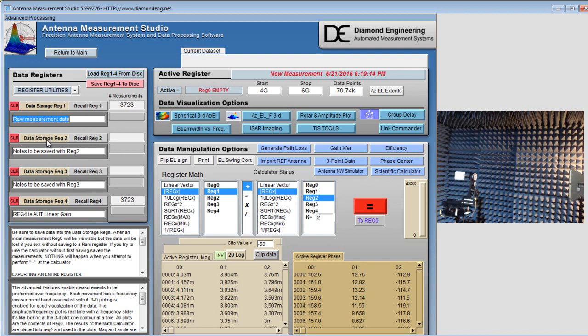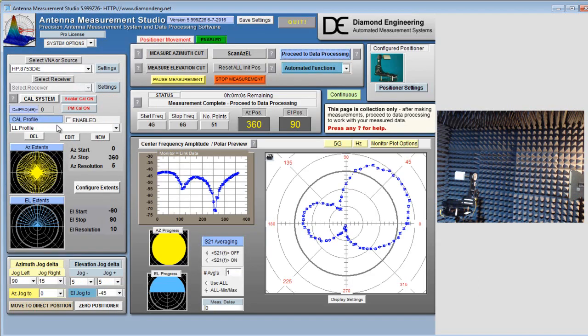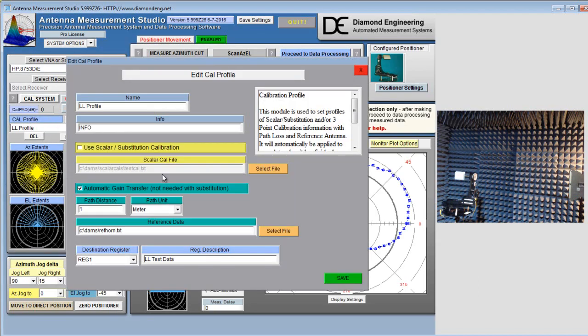For cases where you will be measuring similar antennas with the same reference and same path, you can set up a calibration profile in the front page of the software. This calibration profile will let you specify a reference antenna file and a path distance and perform automatic gain transfer. This way, you do not have to do any post-processing. Your results will be in direct dBi.